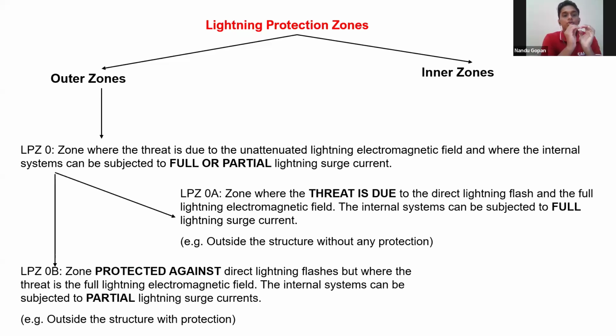Now, LPZ zone 0A means the threat is due to direct lightning flash, and you will be subject to full lightning current. So you are standing in an open field. If you are standing in an open field, then it is called LPZ0A. And if you're standing under a tree, then it is called LPZ0B, because you are protected from direct lightning strike, but you won't be protected from the side flash or anything like that. So that is zone 0B. Okay, I'll show a next slide where I can explain this much better.